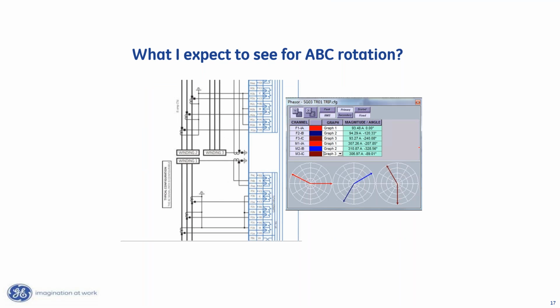Now, this is all at 1 per unit of magnitude. What I'm doing here is mainly talking about the angle. So that's how this 30-degree phase shift across the transformer comes about. Now, it's really important to notice that this 30-degree phase shift occurs because of the way the transformer is wired, right? So what we expect to see for this ABC rotation is this right here. High side windings are at 0 degrees, low side windings are at minus 30 degrees. Because of the way our CTs are wired and the polarities facing, we should see the high side secondary currents at 0 degrees. And that's what we see right here.